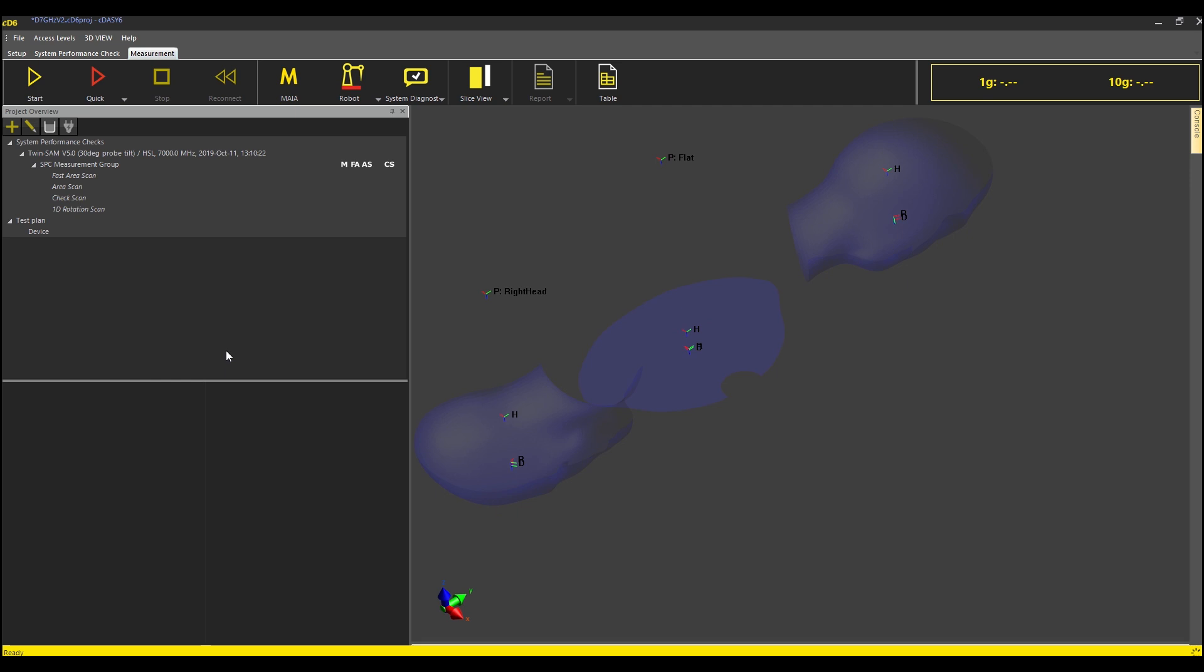I now move to the measurement tab and enable the 7 GHz measurement. The measurement consists of a fast area scan as well as an area scan and a check scan. The check scan is a regular zoom scan followed by a rotation job which measures probe isotropy at the peak location.